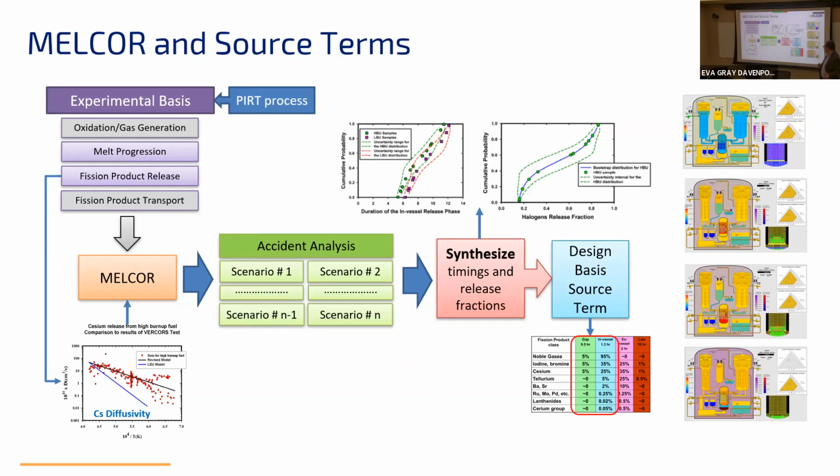And then we move into a later stage of accident progression where the fuel starts being damaged, it heats up, it melts. You get kind of that Three Mile Island molten lava, if you will. And here you get a large release out of the fuel and into the containment. 95% of your noble gases get out. Iodine, bromine, your halogens wind up getting out. And then you have things like cesium, those long-lived fission products getting out. And then finally, later in the accident scenario, you have more extensive degradation, and you have more fission products pumping out.